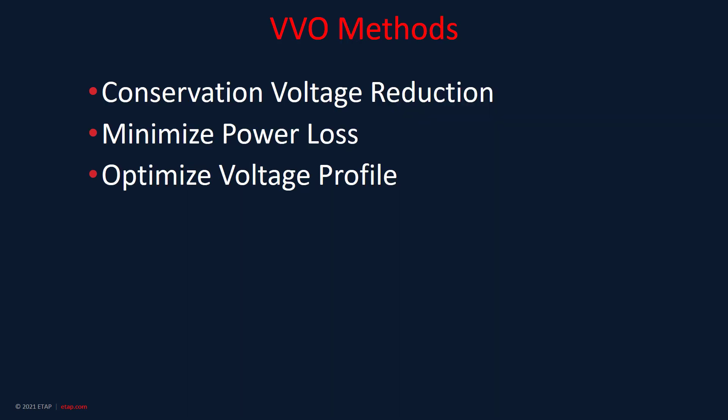Volt-VAR Optimization includes Conservation Voltage Reduction, or CVR, functions that are used to calculate and maintain acceptable voltage — for example, 120 volts plus or minus 5 percent — at the service entrance of all customers served by the feeder under all possible operating conditions. CVR is used to flatten voltage profiles and lower overall system voltage while staying within specified ANSI or IEC voltage limits.